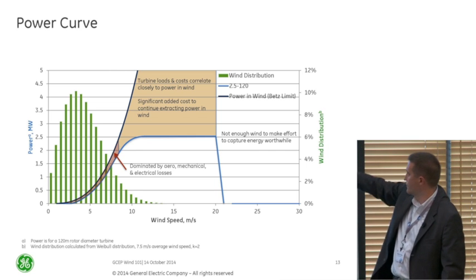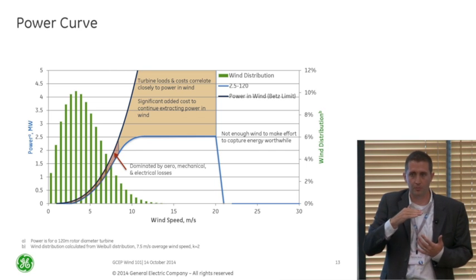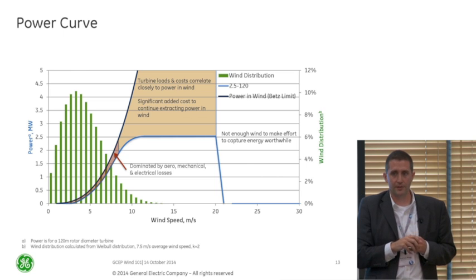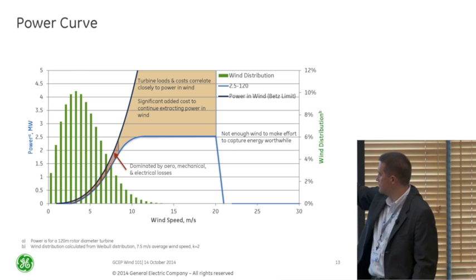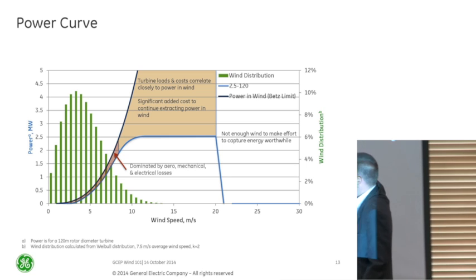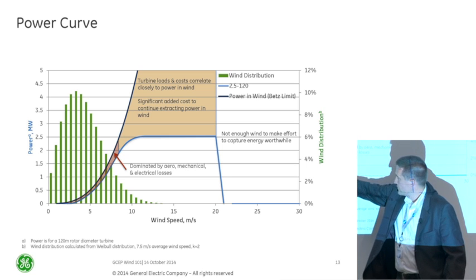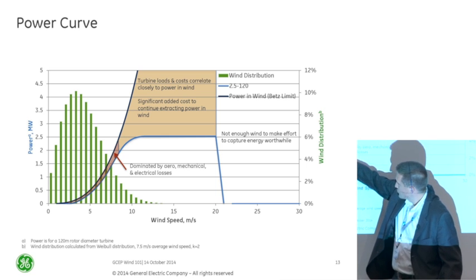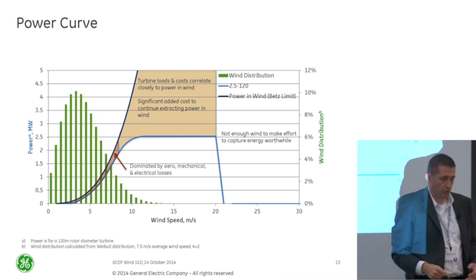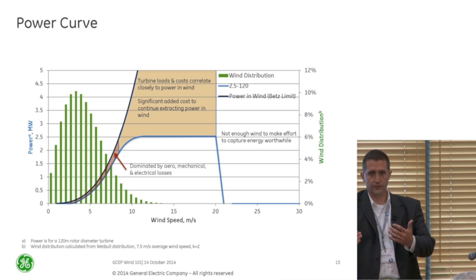That's the dark blue curve. You can see it just continues to go up at a slope to the power of cubed, right? Because it's all dependent on the wind speed cubed. Now, what happens in real life? So our 2.5-120 is this light blue curve. All this difference down here that drops it down is due to efficiency losses. So that's the losses on the CP.